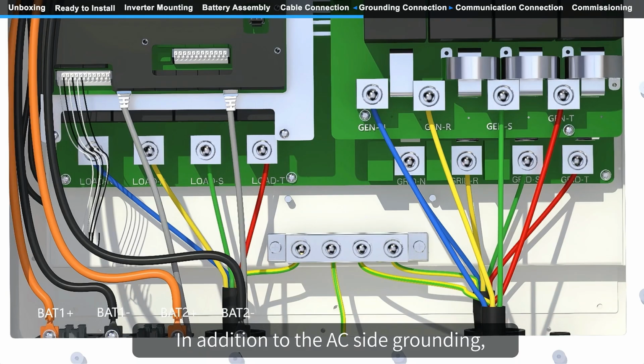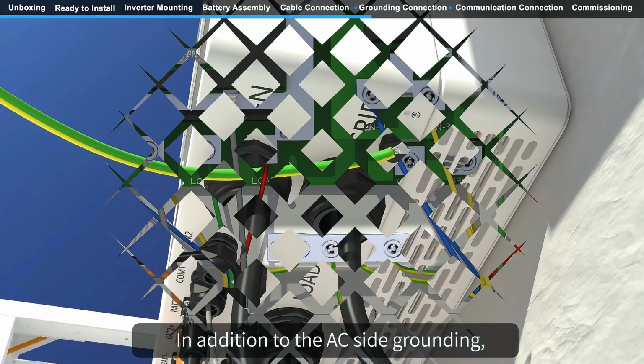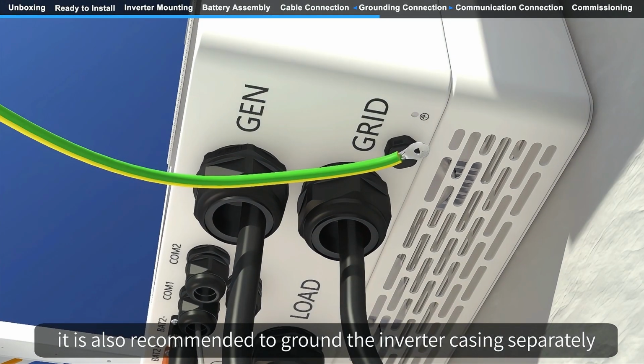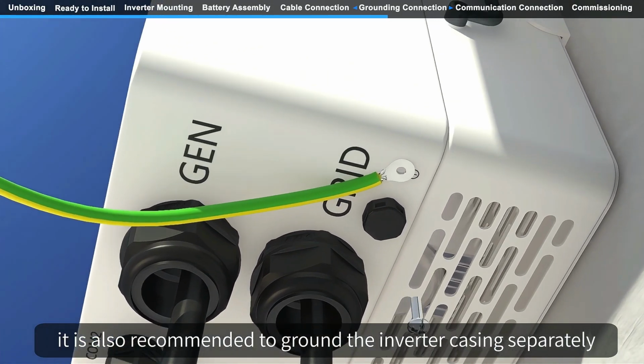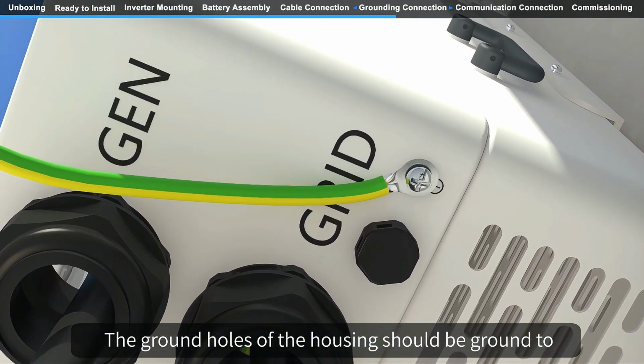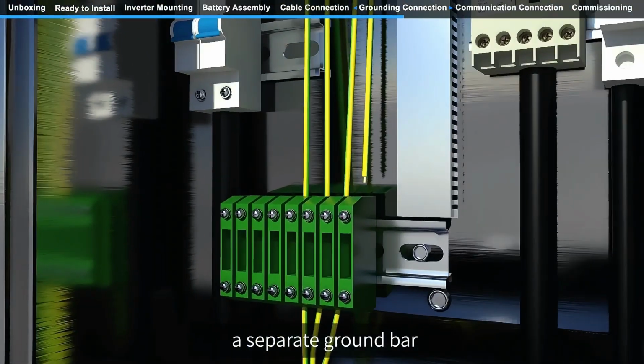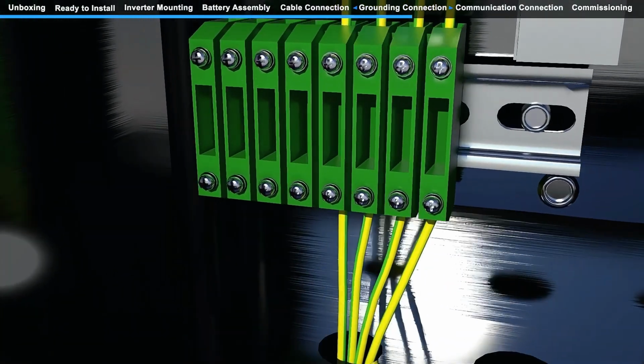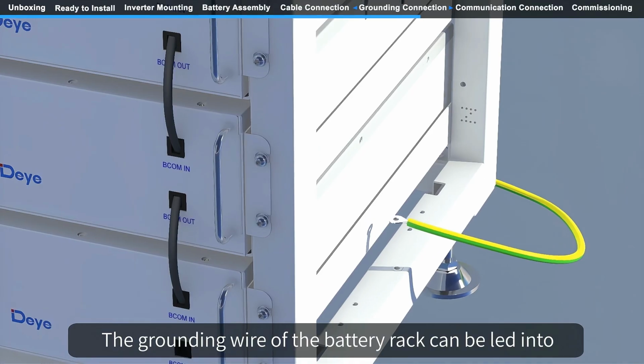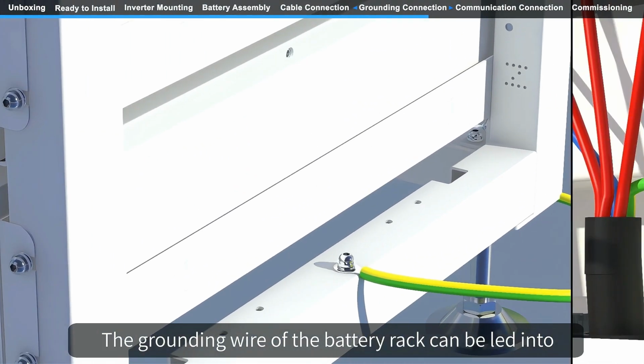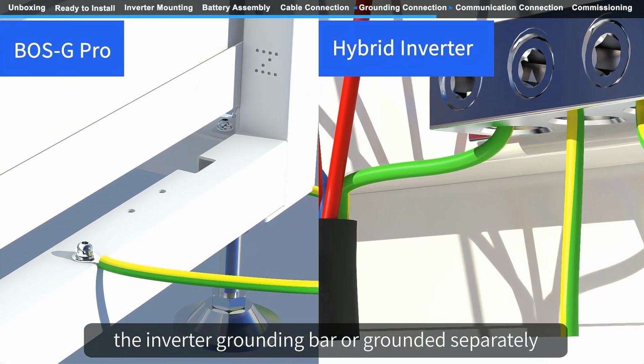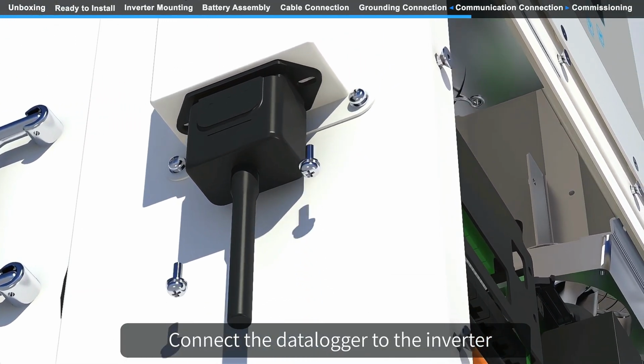Grounding connection. In addition to the AC side grounding, it is also recommended to ground the inverter casing separately. The ground holes of the housing should be ground to a separate ground bar. The grounding wire of the battery rack can be led into the inverter grounding bar or grounded separately. Communication connection. Connect the data logger to the inverter.